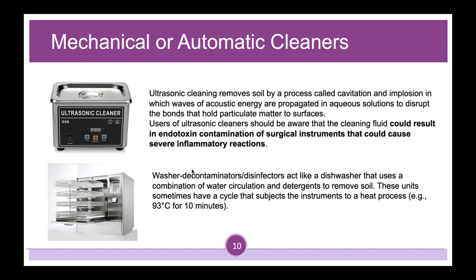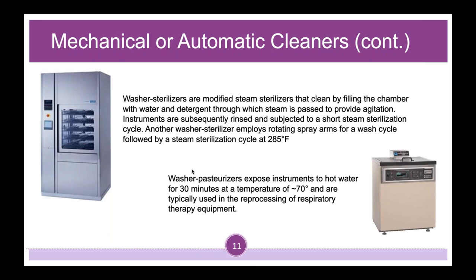Your washer decontaminators / disinfectors act like a dishwasher that uses a combination of water circulation and detergents to remove soil. These units sometimes have a cycle that subjects the instrument to a heat process, and it's going to depend on the type of machine that you have and what's going on.